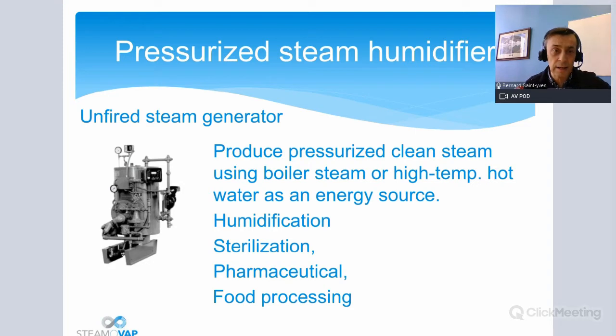The temperatures are much lower than in a steam boiler, and with this unit, which is by the way an unfired steam generator on the picture, produced and offered by Armstrong International also, but there are many companies that are offering unfired steam generators now, or they can sometimes call it a clean steam generator. So this unfired steam generator will be used for humidification or for sterilization in the hospital, because of course the primary steam pressure from the steam boiler or from the steam network cannot be used for sterilization in hospitals or labs. Of course, also for pharmaceutical and in some food processing.